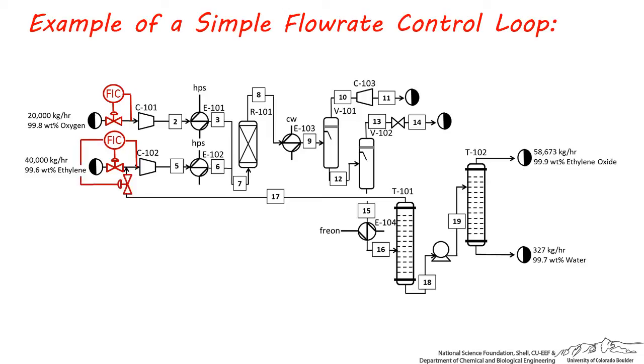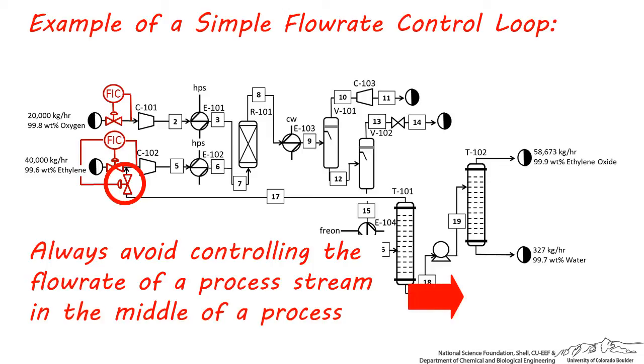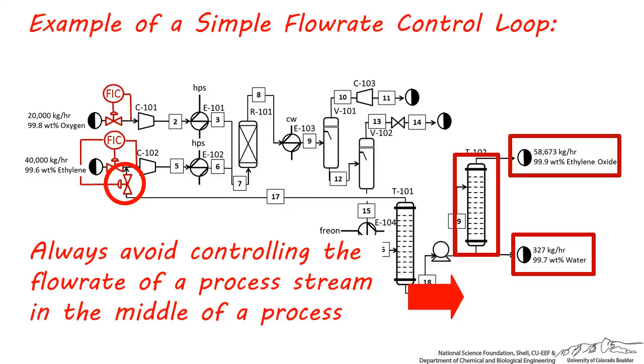There's also another reason not to have a control valve on this recycle stream. You should always avoid trying to control the flow rate of a process stream in the middle of a process because this can cause streams to be diverted. For example, trying to control the distillate flow coming from this distillation column will alter the bottom's flow of the column, which will affect the flow rate going into T102, which will change the flow rate and concentration of these final streams.